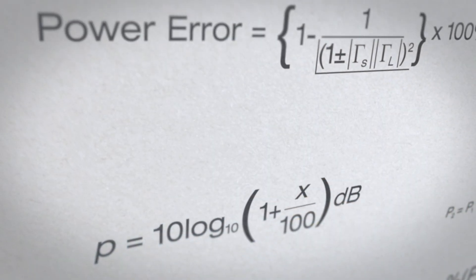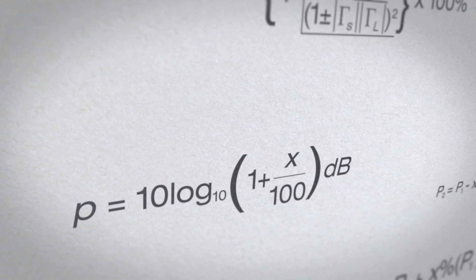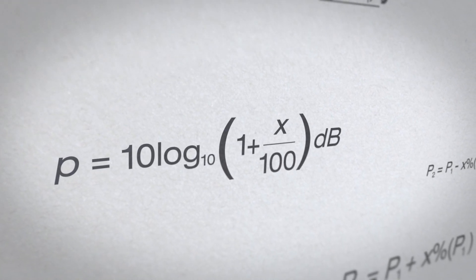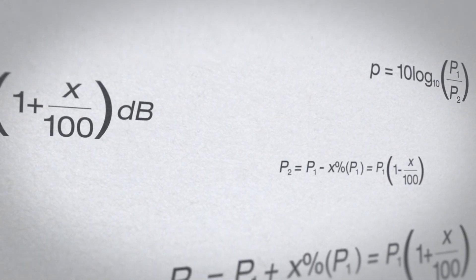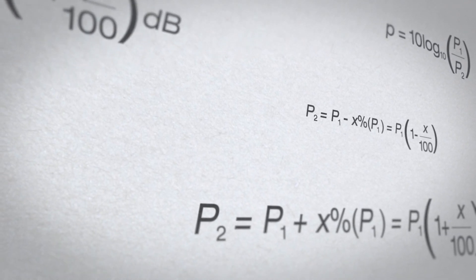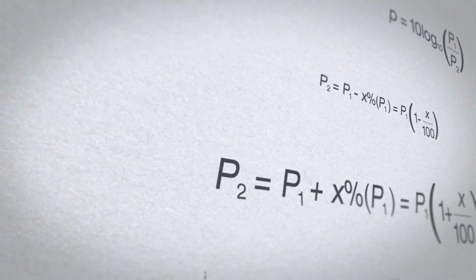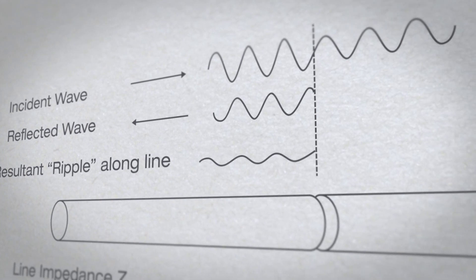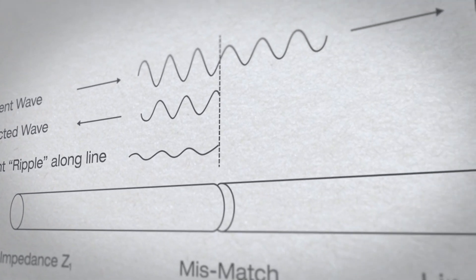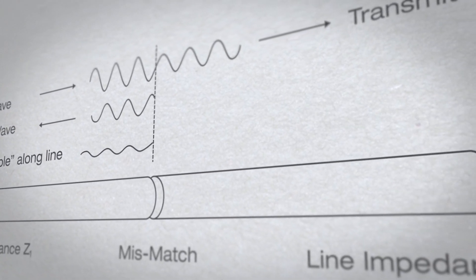General purpose signal sources don't have the accuracy required, and typical RF calibration systems introduce errors and uncertainties through cables, interconnections, and other devices. You have to manually measure, calculate, and apply correction factors for each component in the signal delivery path.